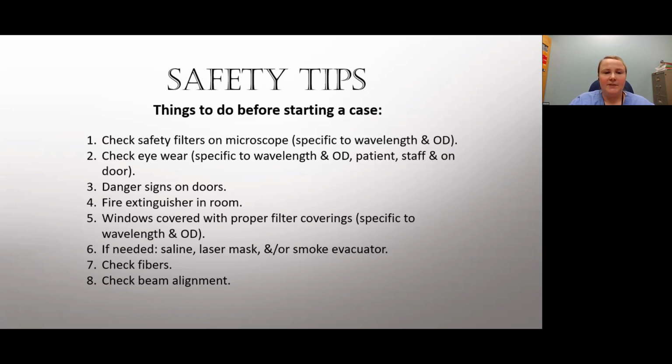If needed, have saline for any fires on the patient or in the room. Use a laser mask if there's plume generated, and or a smoke evacuator, again, if any plume is generated. You also want to check your fibers just to see if there are any cuts or nicks in them, and check the beam alignment. So the beam alignment was the one with the X. Make sure that your aiming beam and your treatment beam are aligned.